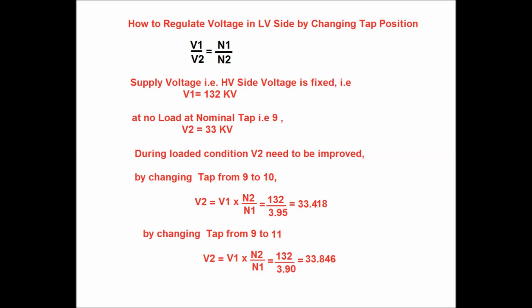So by changing the tap position from 9 to 10, the turn ratio is reduced. Since the N1 by N2 ratio is reduced, V2 equal to V1 by N1 by N2 will be increased. So at tap position 10, the V2, that is the LV side voltage, shall be equal to 132 by 3.95, which is equal to 33.418 kV. Again, by changing the tap from 9 to 11, the V2 shall be 132 by 3.90, which is equal to 33.846 kV. So you can see that by changing the tap position from nominal to 10 and 11, the LV side voltage can be increased.